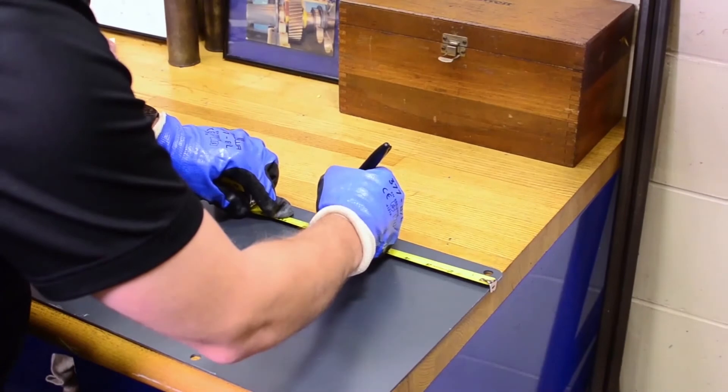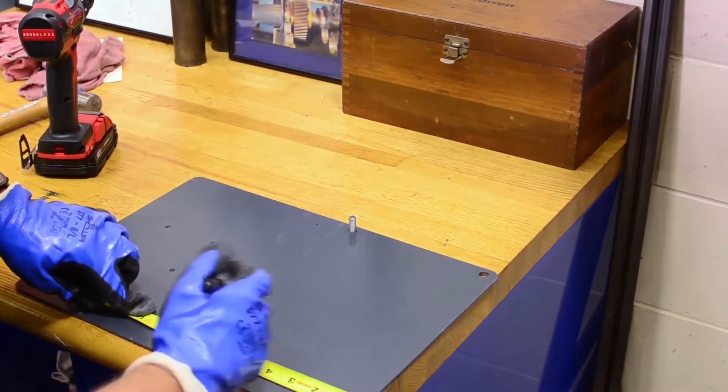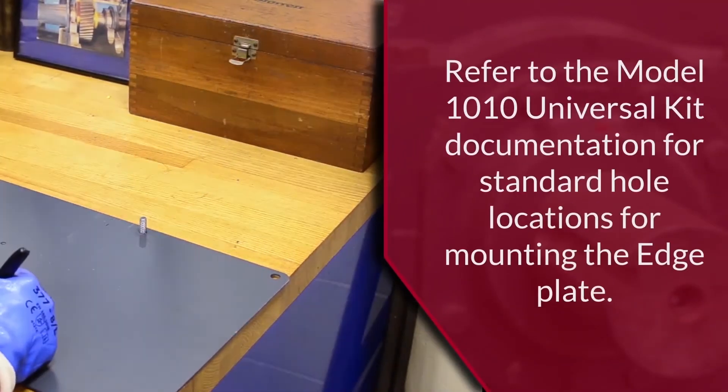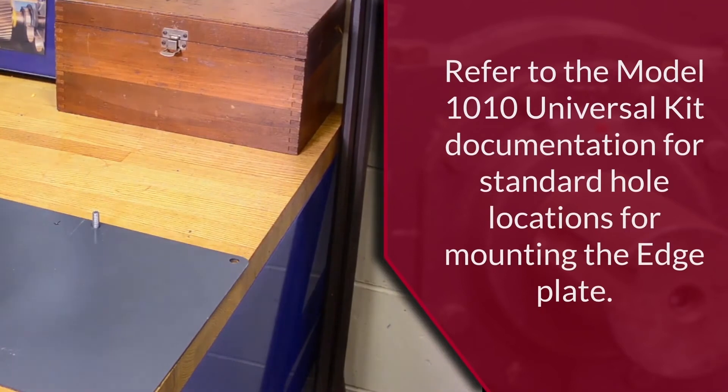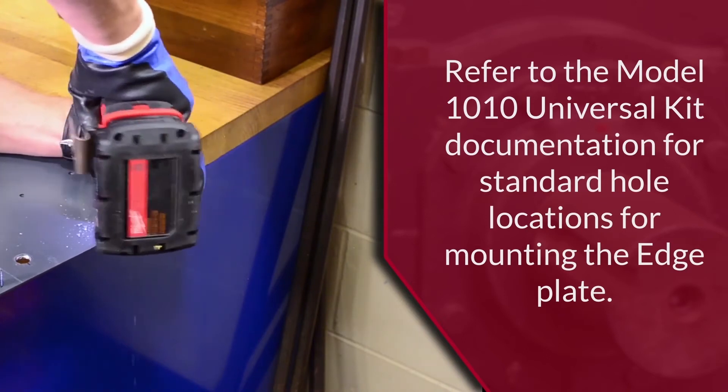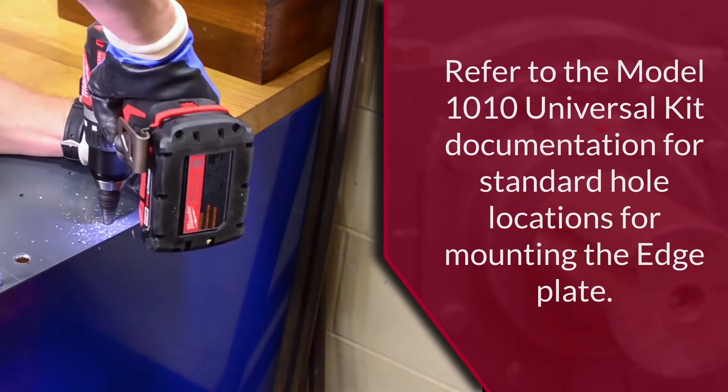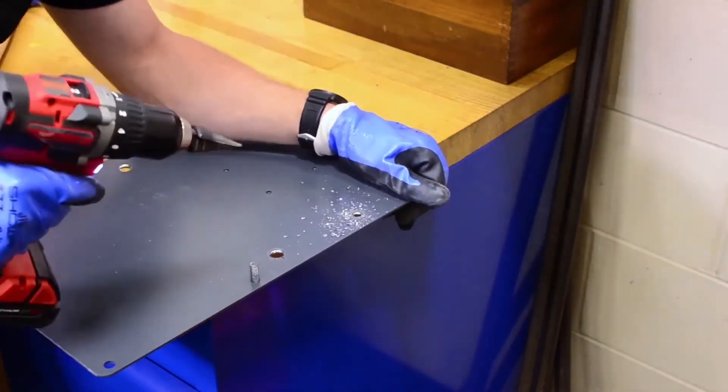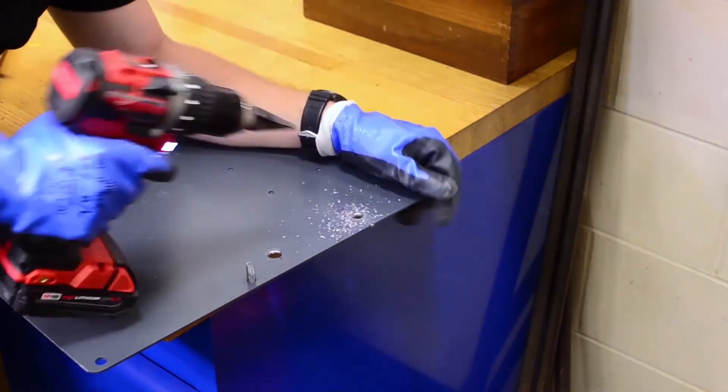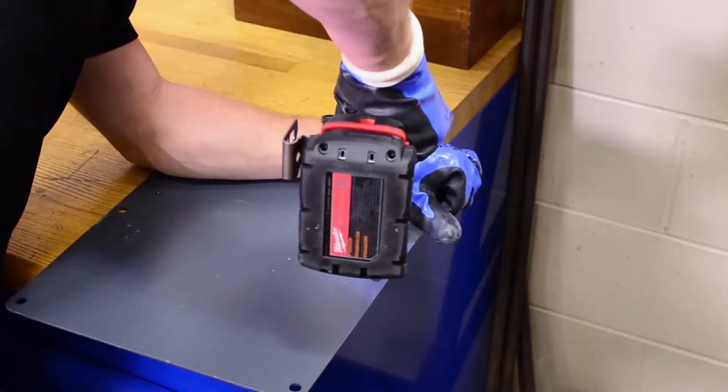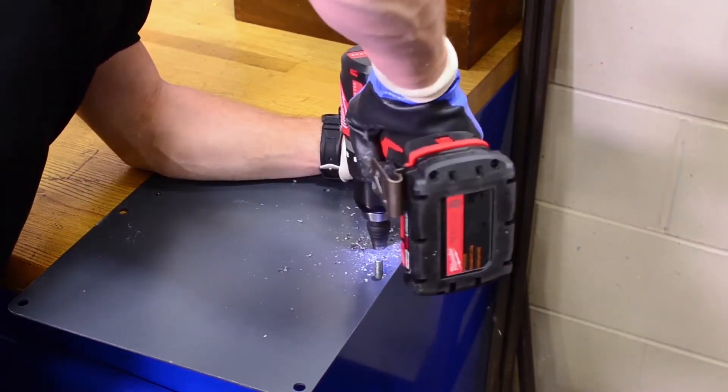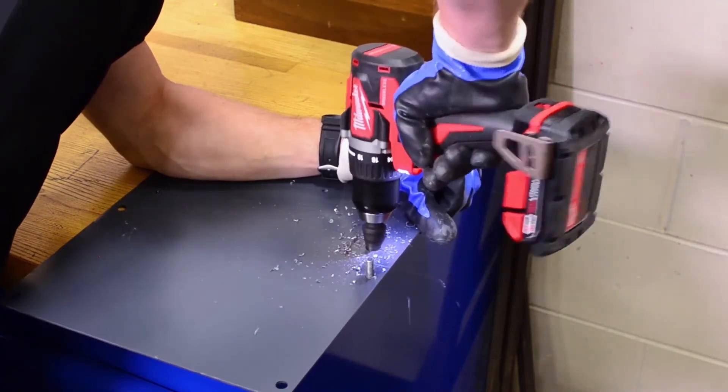To install the edge device mounting plate to the unistrut, two holes will need to be drilled into the plate to attach half-inch fasteners. This allows the plate location to be customized based on the application. However, when selecting hole locations, verify the fasteners will not interfere with the edge device. Using a step drill bit, drill two clearance holes to a diameter of 9-16ths. An additional hole for the andon light will also need to be drilled at this time. Drill a 3-8-inch clearance hole on the top of the plate to accommodate the andon light bracket.